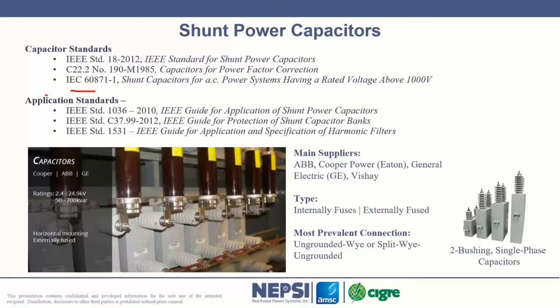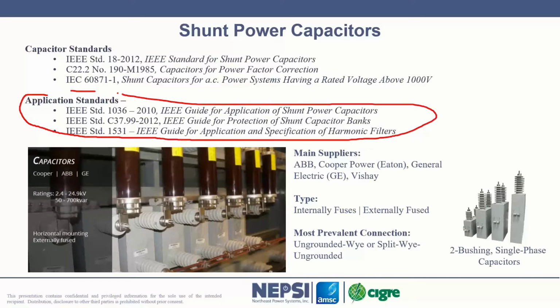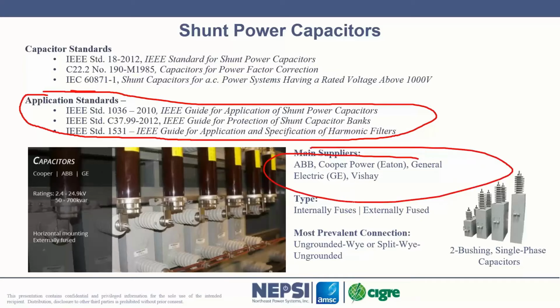There's also some application standards other than just the component standards, and they're noted here. So these are good reference tools to go to when coming up with the choice of capacitors. From our standpoint, we're using these key suppliers, right? And there's not a whole lot of other ones that we're using. The capacitors can be internally fused or externally fused. And internally fused capacitors mean the capacitors are equipped with internal fuses, usually many small fuses.